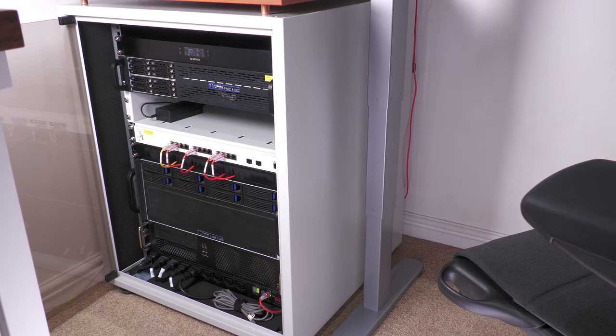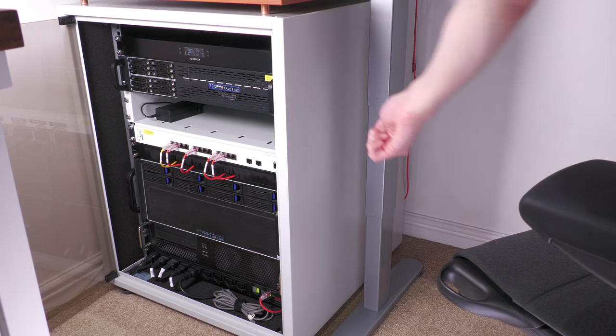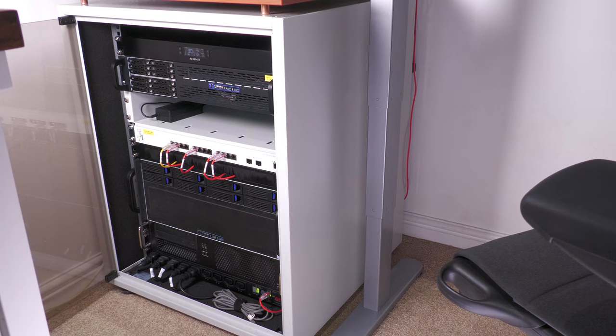It'd be interesting to know how this actually works from an acoustic perspective. The foam's definitely blocking some level of sound coming out of the rack, but I think what it's also doing is blocking reverberation inside the rack. Annoyingly, I didn't record this before I put the foam in, but when you used to knock on the side of the rack, it sounded quite hollow, it was quite a loud bang sound, and the sound sustained for quite a while afterwards. It was almost like a drum. But now when you knock on it with the foam, it's like a solid dead sound. It's made such a difference even to that, and I think that's stopping the sound reverberating inside a lot, and that's definitely really helping. And the foam is also just going to stop a lot of the sound coming through the sides. But yeah, the difference is absolutely huge.